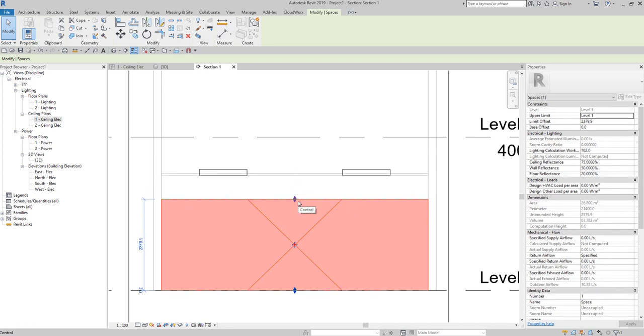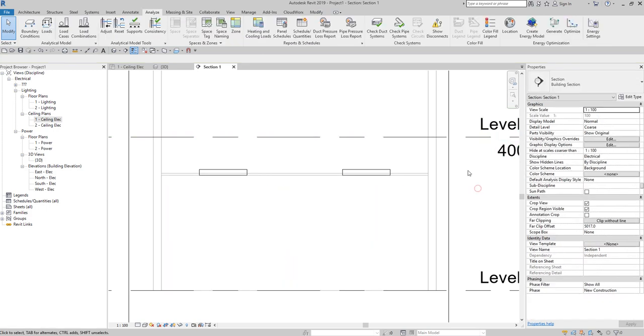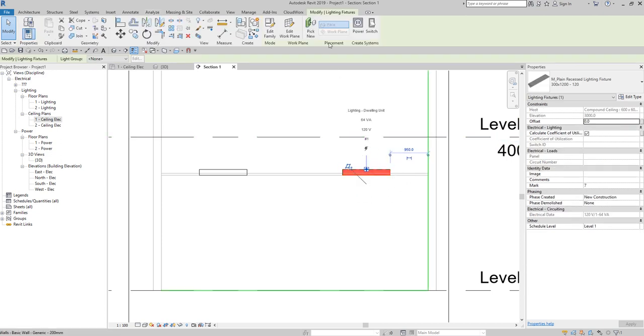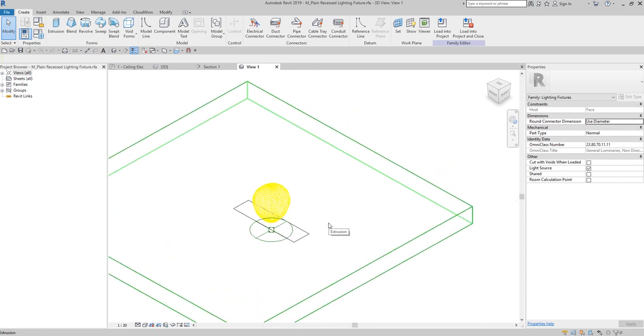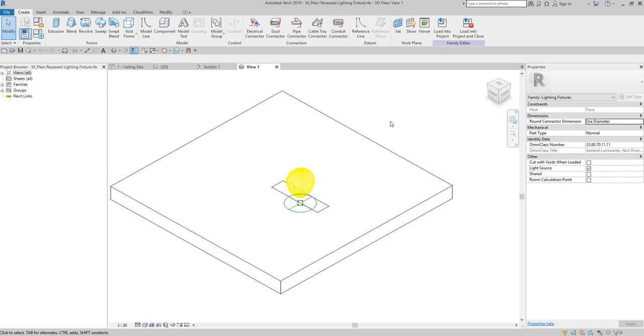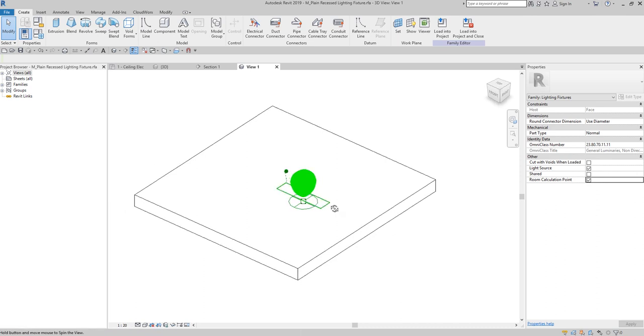Another option to solve this kind of problem, instead of dragging the space, is to modify the family. I'll deliberately move the space down again so the value is zero. I'll click the lighting fixture and select Edit Family, which will open the family editor. This is actually part of the examination in Revit MEP — there is a question asking about the room calculation point. Every lighting fixture family has what they call a room calculation point. I'll click that to identify it.